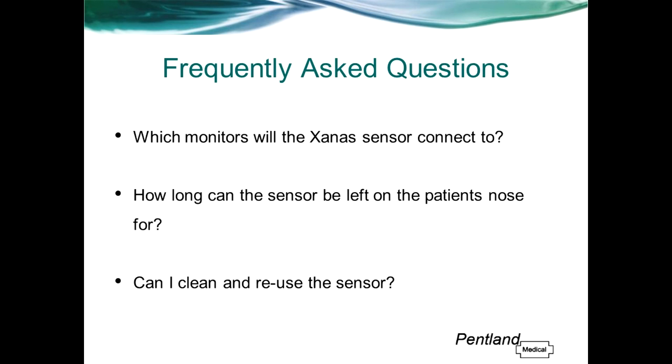Can I clean and reuse the sensor? The Xanas sensor is a disposable single-patient-use device. The device cannot be cleaned or sterilised without potential damage to critical components. Reuse may cause unreliable readings, and if the sensor is used on more than one patient there is a risk of cross contamination.